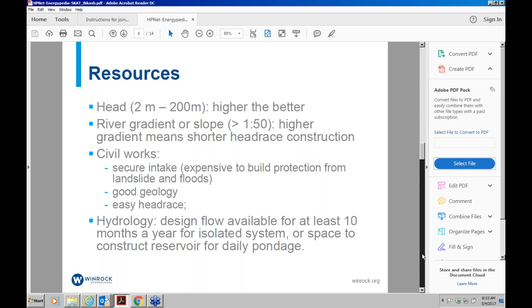In terms of hydrology, once you've done your demand analysis—for isolated hydro systems not connected to the grid—we're often looking for the design flow to be available at least 10 months a year. However, this isn't always possible. In some instances, a site may only have the design flow available for 6-7 months of the year. But if there's space to construct a reservoir, then during months without full flow 24 hours a day, you can store water to use either for peak hours or as needed, with a governor controlling how much water is let into the turbine—saving water when it's not needed and using it during peak hours.